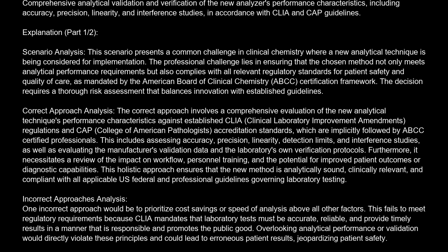Correct approach analysis. The correct approach involves a comprehensive evaluation of the new analytical technique's performance characteristics against established CLIA, Clinical Laboratory Improvement Amendments, regulations, and CAP, College of American Pathologists, accreditation standards, which are implicitly followed by ABCC-certified professionals. This includes assessing accuracy, precision, linearity, detection limits, and interference studies, as well as evaluating the manufacturer's validation data and the laboratory's own verification protocols.